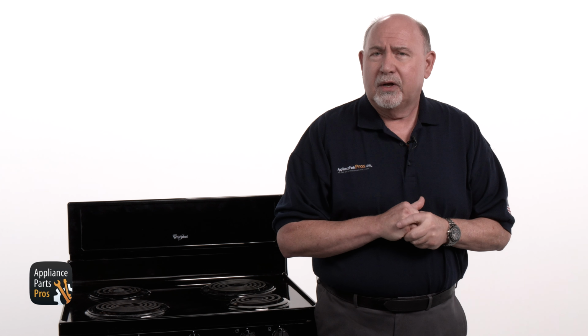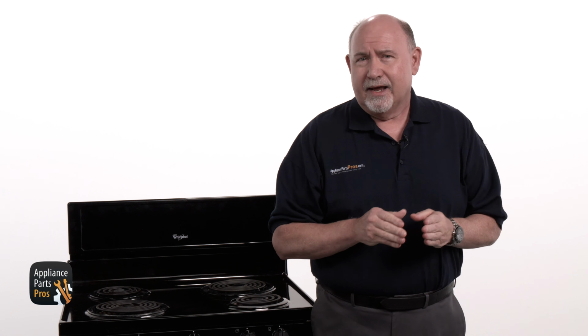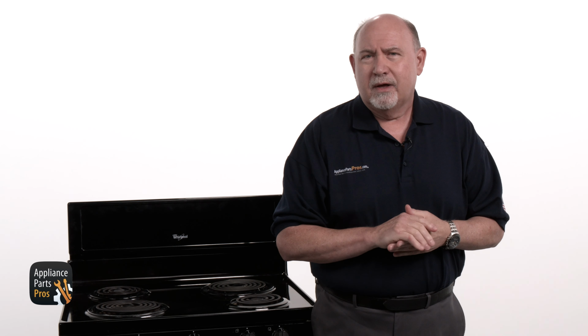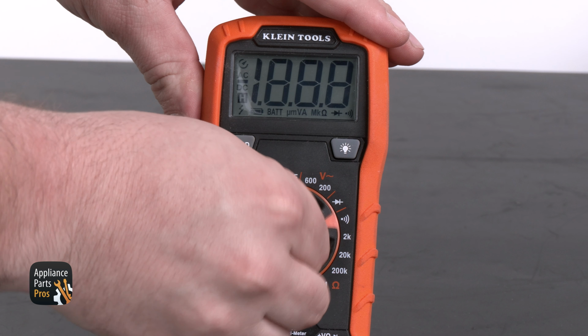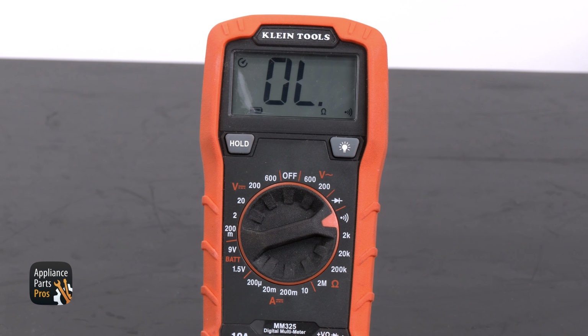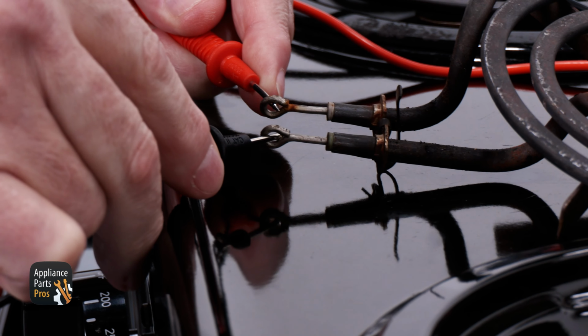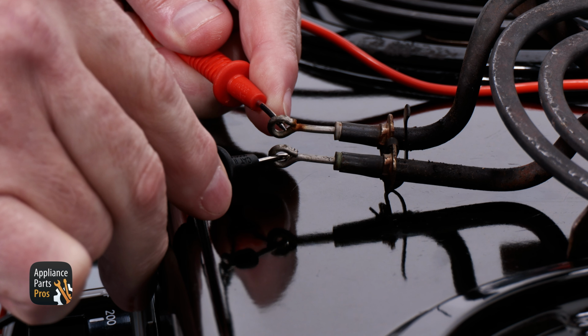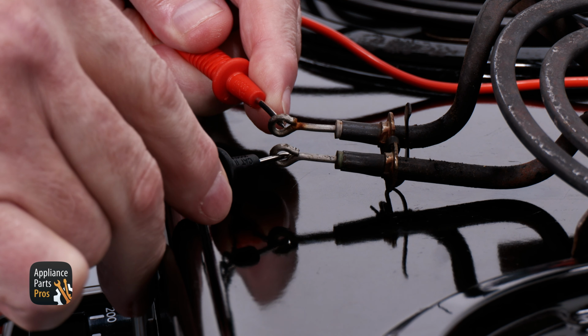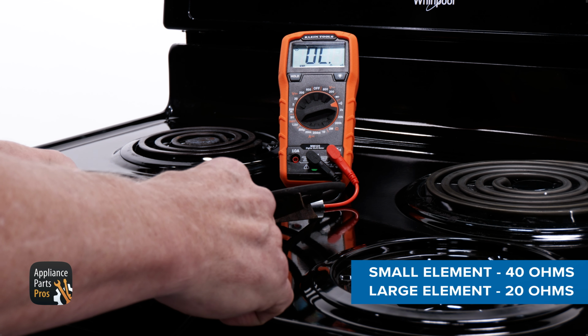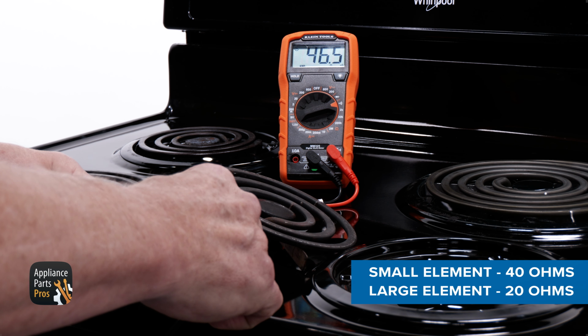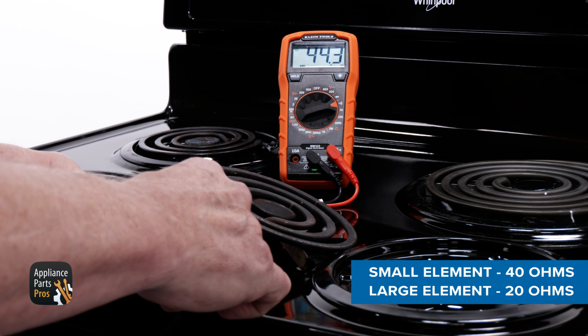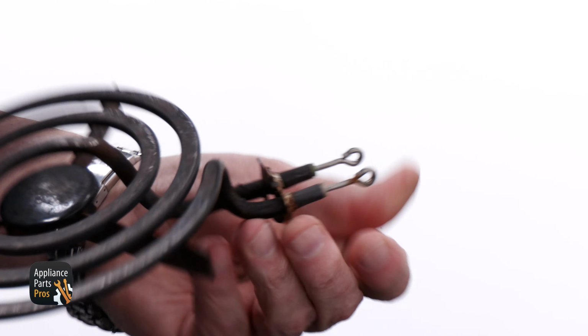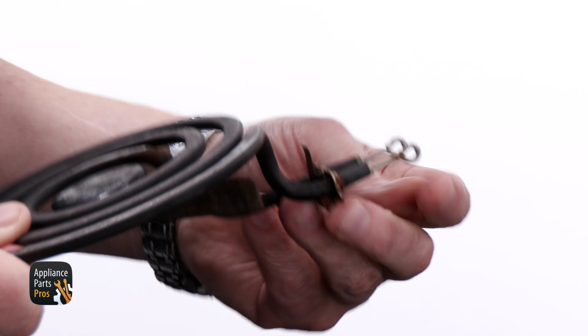You'll need to set your multimeter to the resistance setting, which is measured in ohms. This multimeter doesn't have a low resistance setting, so we're going to use the continuity setting. Then use the meter probes to check across the two terminals of the element. You should see 20 to 40 ohms displayed on the meter. If the reading is out of range, or you see a defect in the coil, then you'll need to replace the element.